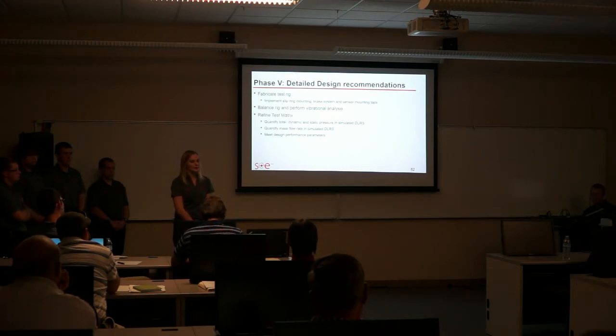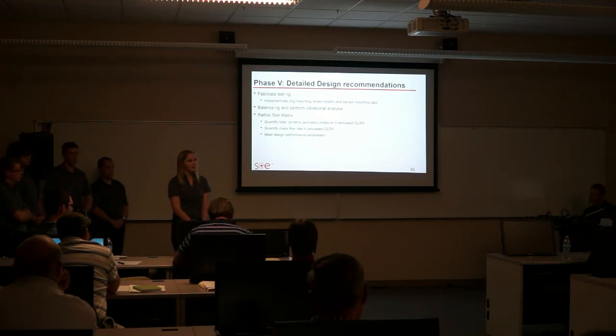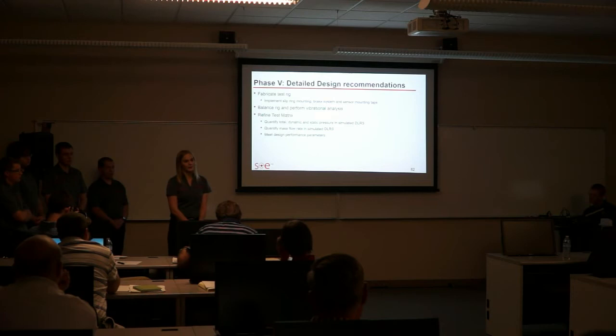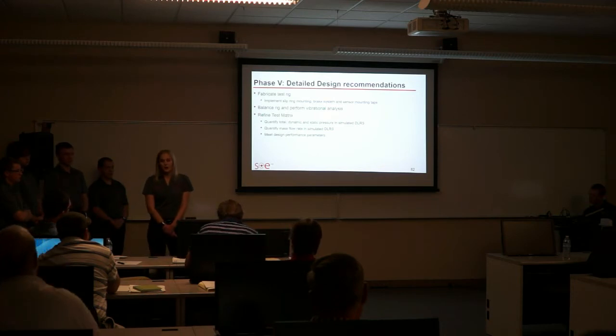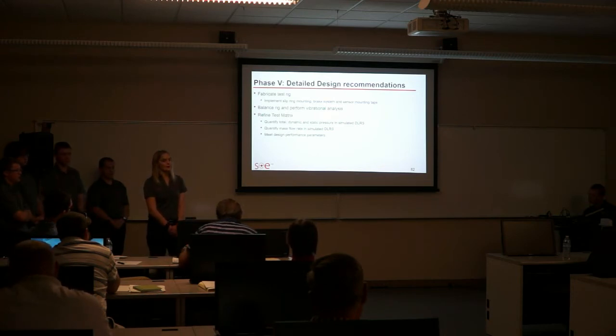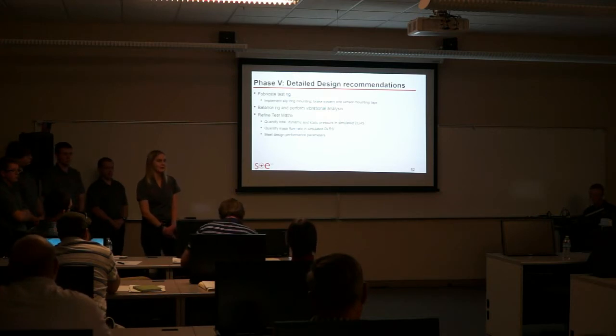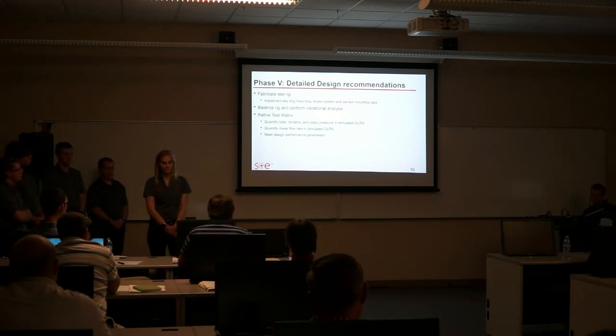Further, we will continue to refine our test matrix and complete the necessary testing to determine and confirm the rig survivability and performance values. We'll be able to meet our project scope and deliverables by quantifying total dynamic and static pressures, as well as quantifying the mass flow rate from the simulated DLRs. All of this data will then be used to confirm that we have met our design performance parameters.